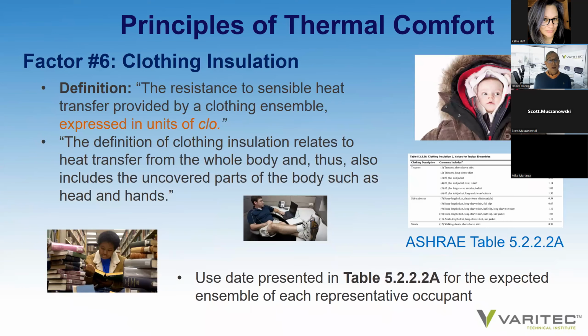Another factor is clothing insulation. Is somebody walking around in an office in shorts, t-shirt, and flip-flops, or are they wearing sweaters and jackets maybe in an office when they're working? The clothing insulation factor is called a CLO, and clothing inhibits the sensible heat energy radiation of occupants, allowing us to stay warmer with the more clothes that we wear. So depending on what the occupants might be anticipated to be wearing, that will also impact a sense of thermal comfort in a space. ASHRAE Standard 55 has a table as well that references CLO value factors.